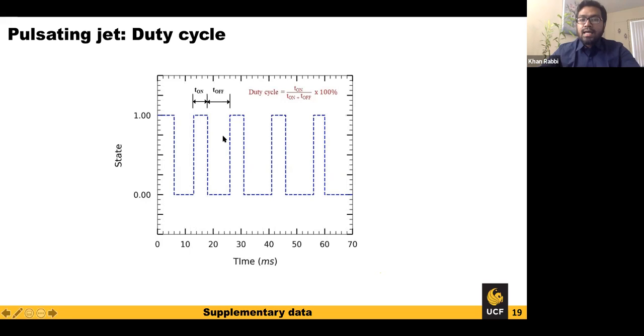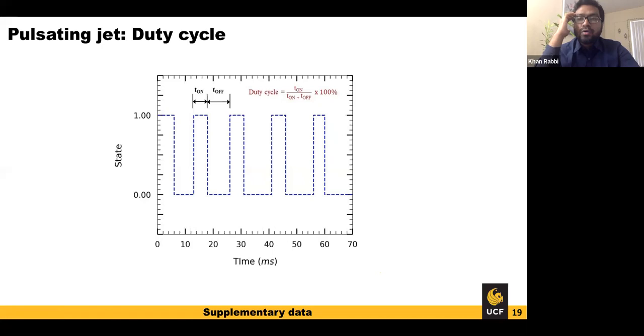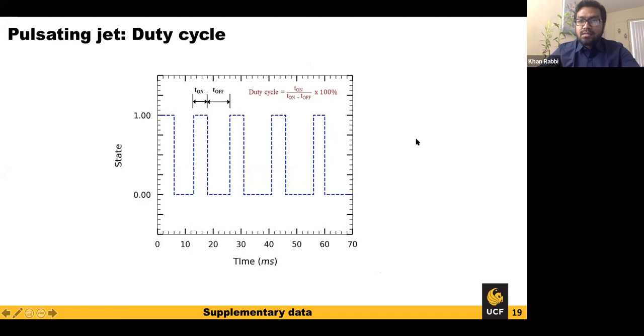The binary nature of the pulsation justifies the square shape — either you have a droplet or you don't. There is no intermediate condition. The key design parameter you can tune is the T-on and T-off — the time duration during which liquid is present and the time during which there is no liquid on the surface. In terms of pumping power, pulsation doesn't directly decrease the pumping energy need, but it does mean you use much less coolant overall.